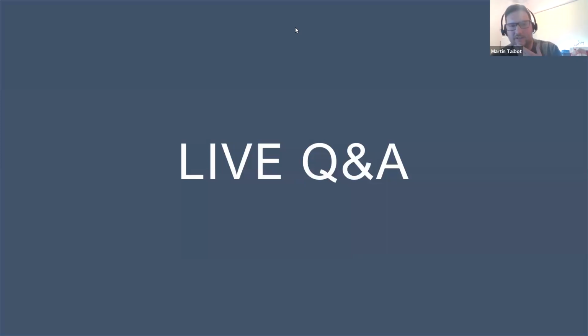Yeah, I would say at the point of work, to be honest. When you're identifying the switch to be operated, you both see the safety program, and it's just that second opinion. You don't really always get that if you're telephoning someone up. They're not really giving you that second opinion that you're in front of the right switch and you're operating the right one. However, when he goes to operate the switch, the accompanying safety person should make sure that they're at least stood back out of the arc flash boundary, so that if anything does go wrong, they're not injured themselves and they're able to render assistance.